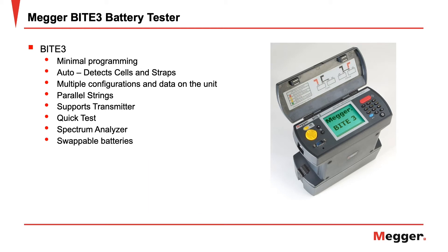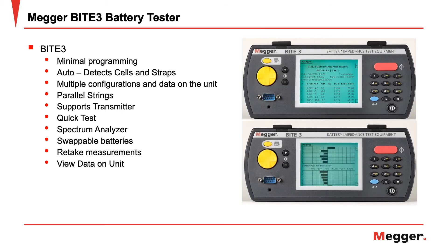The BITE3 has hot-swappable batteries — you can replace them in the middle of a test and pick up where you left off, so you'll never lose data. The BITE3 also allows you to easily retake cell and strap measurements and view the string data on the unit. You can see all the cell and strap measurements for the entire string, as well as the cell data displayed as a simple bar chart. Easily view all the data on the spot and perform any required troubleshooting and retesting, so there's no need for additional trips.